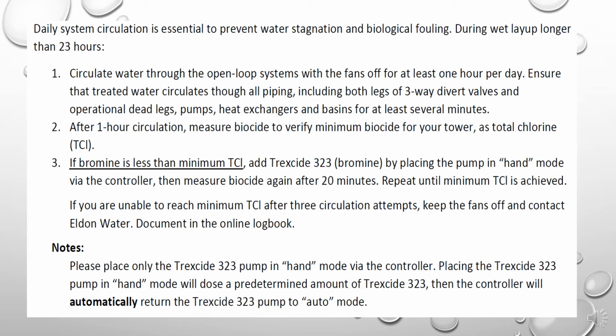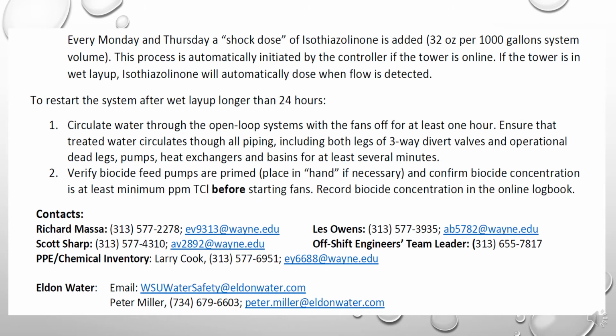And place the Trexcide pump in hand via the controller. Placing it in hand doses a predetermined amount of bromine, and then the controller automatically returns that pump to auto mode after that amount is dispensed. Just a reminder that every Monday and Thursday that shock dose of isothiazolinone is added to the system. It is automatically initiated by the controller if the tower is online.